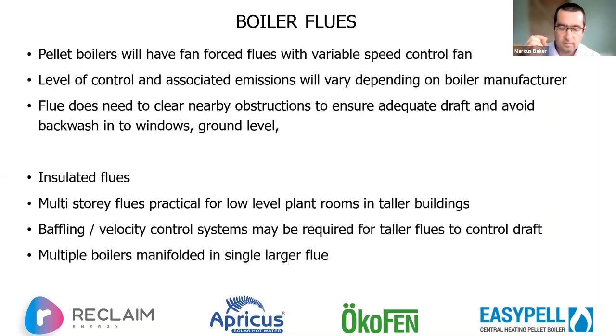We've just got very difficult to prove particulate levels at times, not because of the boilers, but because, as usual, of the way that we've legislated. Under the National Environmental Standards for Air Quality, regional authorities have to demonstrate that they're not exceeding limits for the entire airshed over the entire year. So getting that down to the really granular level of individual boilers can become quite complicated.